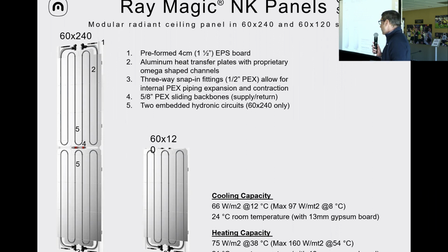To give you an idea of performance, cooling capacity and heating capacity, the maximum with this panel is close to 100 watts per square meter with an entering fluid temperature of 8 degrees. I would say typical is around 60, 70 watts per square meter, and this is with about 12 degrees water temperature entering the panel. And when you cover the panel with drywall, like a 13 millimeter gypsum board, the temperature on the drywall will be about 5 degrees above. So if we put in 12 degrees, we will probably reach about 17 degrees, more or less.